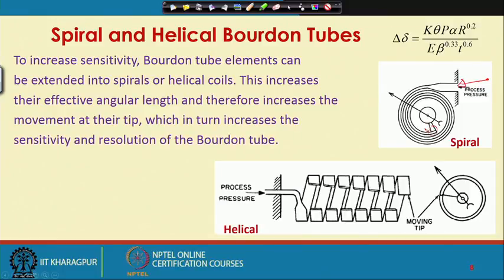The same here in case of helical structure, this is the open end which is rigidly fixed and you apply pressure here. This is the end which is sealed and not rigidly fixed. So, this is the moving tip. So, I attach the pointer and scale to this moving tip.